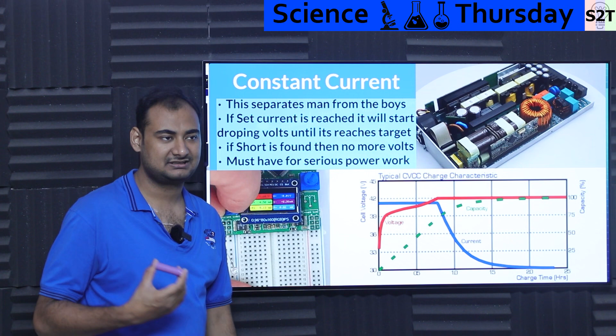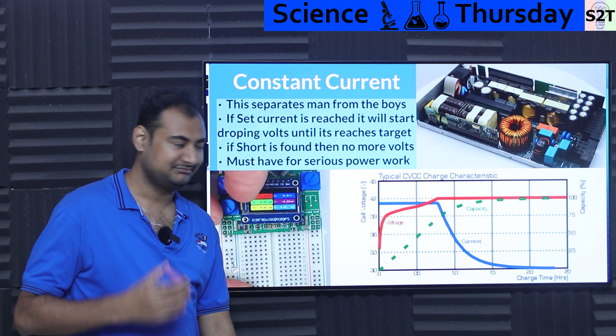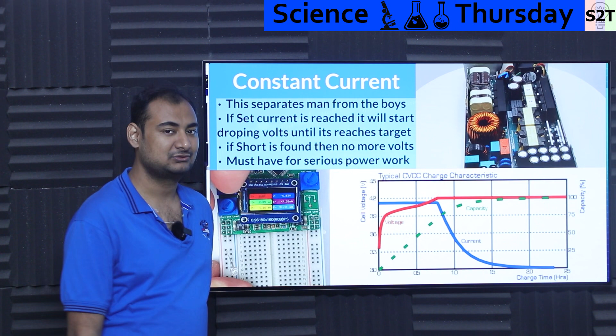That's why you cannot just directly swap a lead acid battery system with lithium ion, even with a BMS, they're not doing this the same way. Lead acid is inherently designed with constant voltage, it's like here's the voltage, go YOLO. Lithium doesn't like that. You can force it, and a BMS could try its best to handle it, but it won't be a pretty situation.